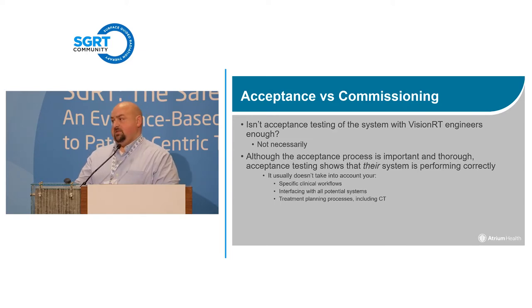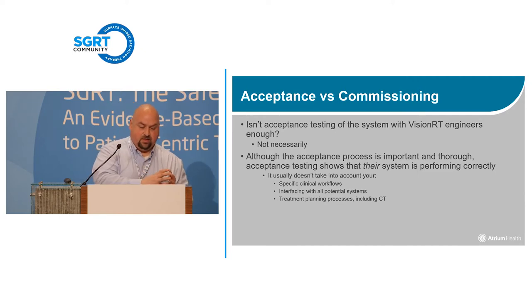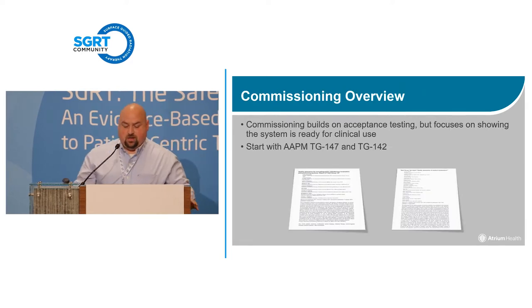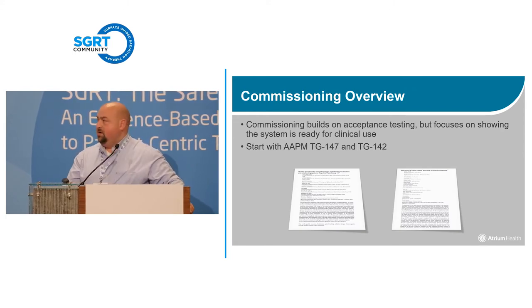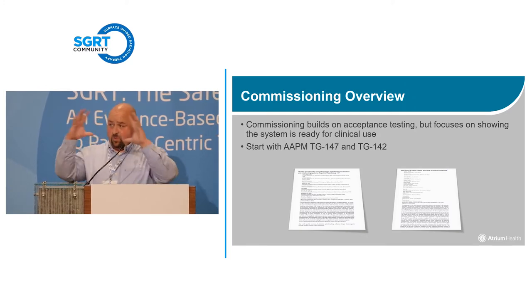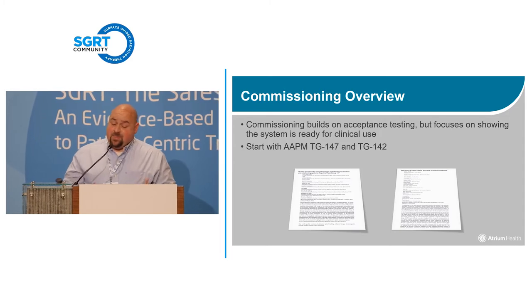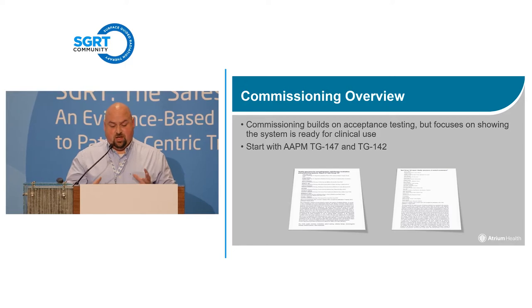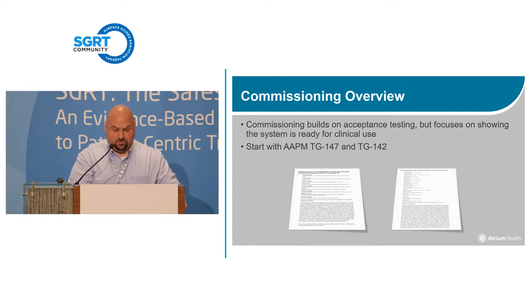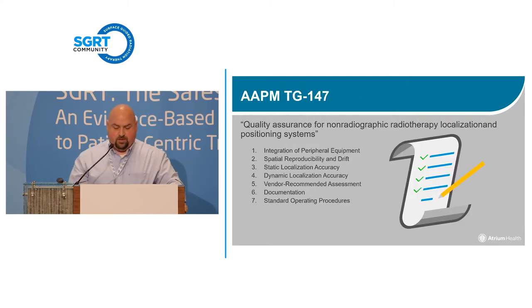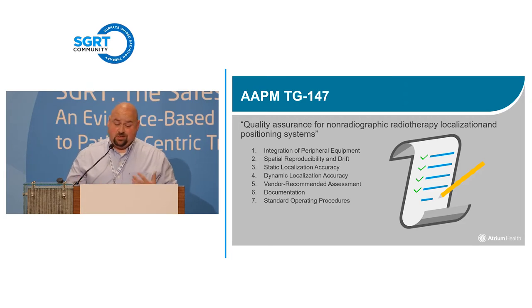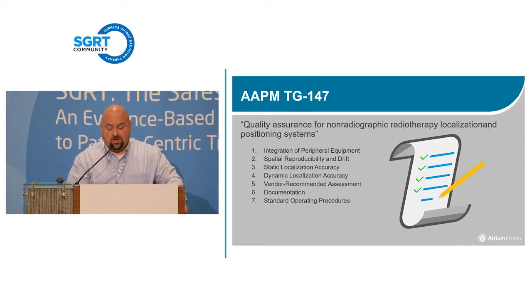You need to hold the vendor accountable to make sure systems interface correctly — that's part of commissioning, as are treatment planning processes. Showing that something from CT can be accurately delivered on the machine is the ultimate goal. TG-147 has very good surface-guided optical tracking guidelines, and TG-142 covers general QA guidelines for all machines. Just because something isn't in the guidelines doesn't mean you skip it — you may need to go above and beyond or combine tests.